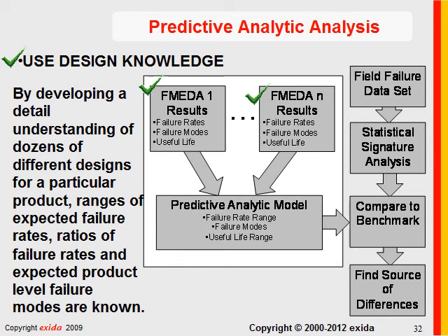And it has everything to do with how good is your data. And that has everything to do with, in my opinion, getting that data analyzed by someone who thoroughly understands the data analysis techniques. Mathematically, there's no reason you can't move to the new value if you have high confidence in your data, 90% plus, which is what 61508 suggests.